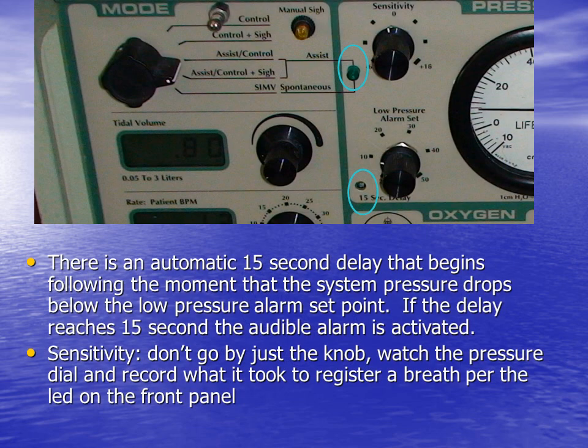The low-pressure alarm has a 15-second delay before the audible alarm is triggered. A green LED lights up to let the clinician know that the 15 seconds have begun. On the subject of sensitivity settings, it is recommended you do not simply trust the knob settings. Rather, watch your pressure dial and record the pressure you visualized that it took to trigger a breath. Remember, the green LED next to the sensitivity knob will flash to show patient effort.